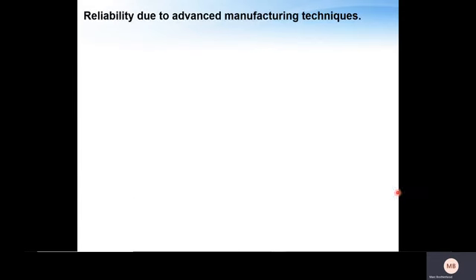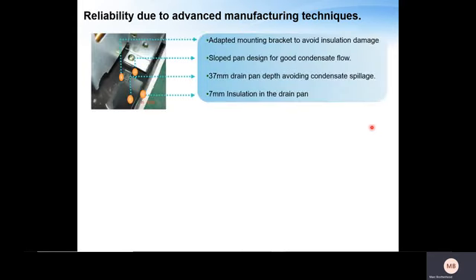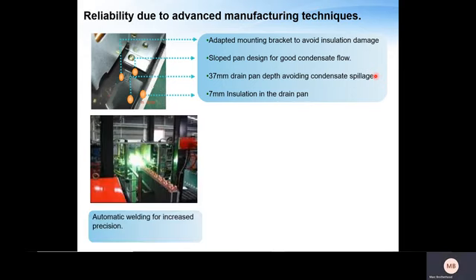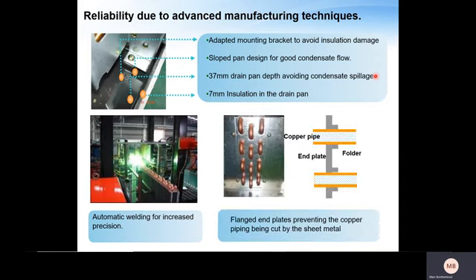We have reliability due to advanced manufacturing techniques. So if we look at the drain pan, for example, adaptive mounting bracket to avoid any damage to the insulation, sloped drain pans with good gradients for condense flow, a nice 37mm drain pan depth to avoid any buildup of condensation spilling over the sides, as well as a standard 7mm insulation in the drip tray. We have automatic welding for increased precision on the heat exchangers, and the flanged end plates preventing copper piping being cut by sheet metal. So here you can see this extra rigidity, and it's bent and flanged, so it won't, with oscillations, cut into the pipework, creating water leaks.